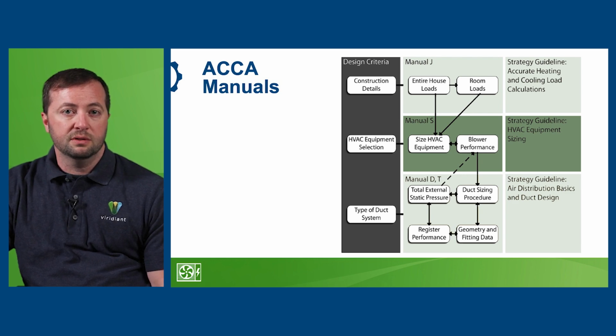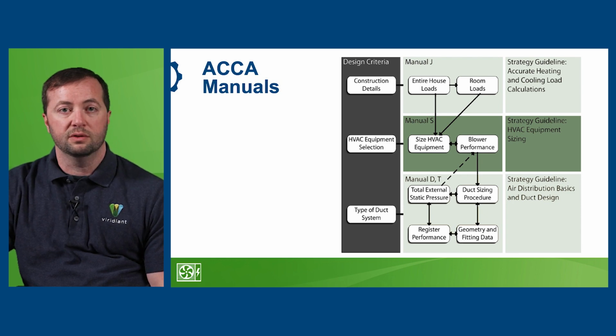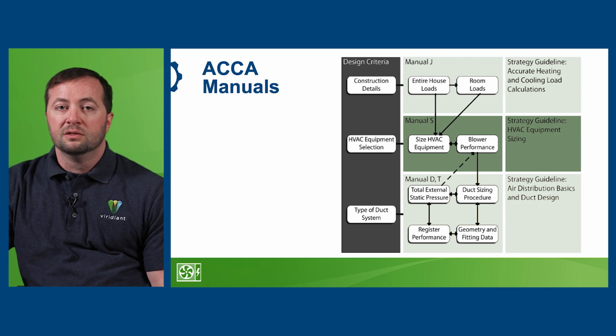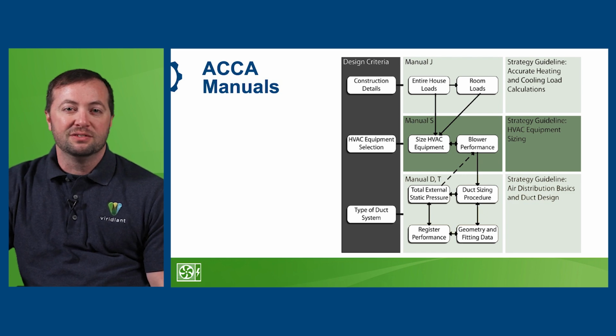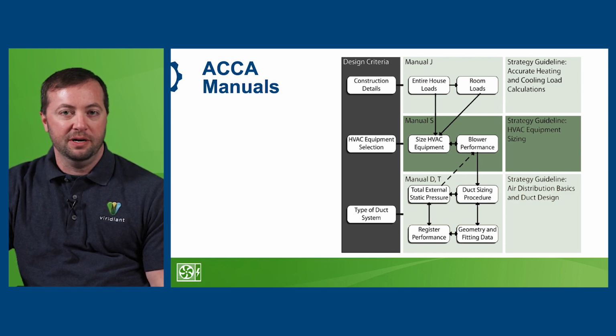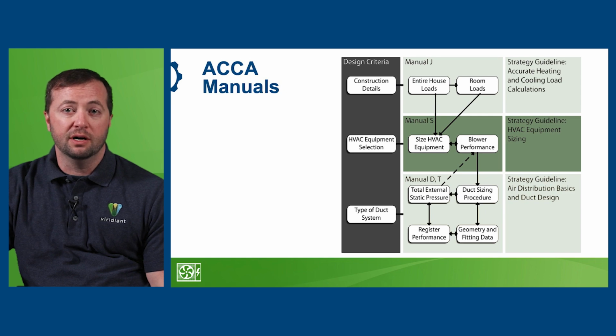For heat pumps that will be installed without auxiliary heat or other backup heating systems, you'll also need to consider sizing for both cooling and heating. Typically, we size for cooling. With those specific system types, you also want to take into account the heating needs. Please don't make the classic mistake of installing oversized equipment. It's the pathway to poor performance and high cost.